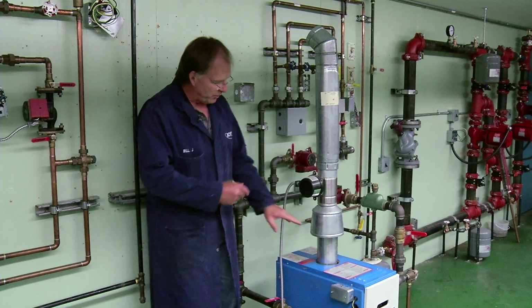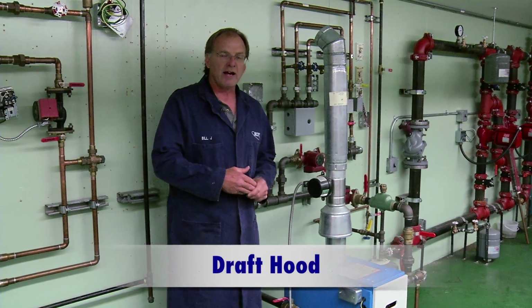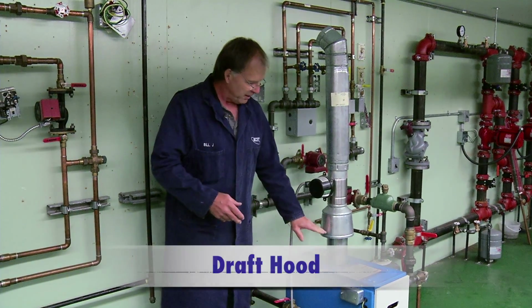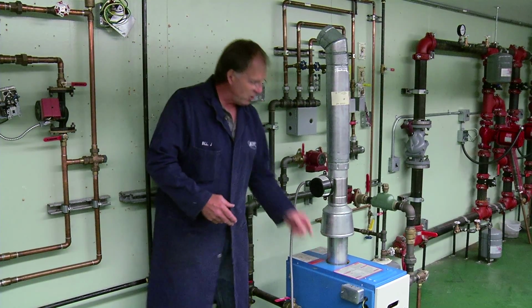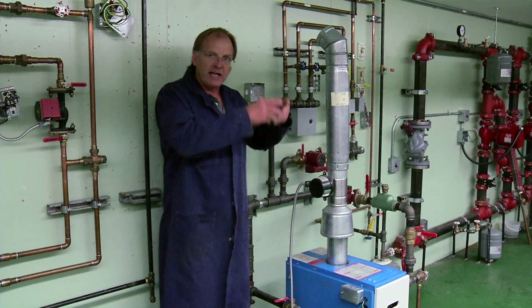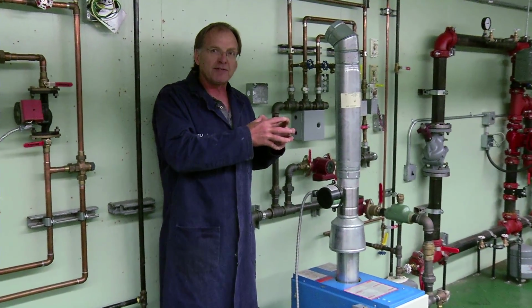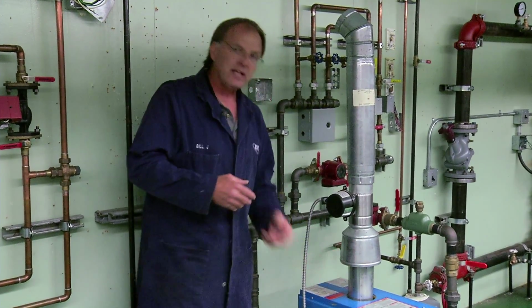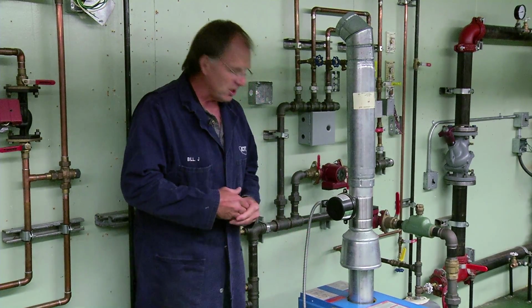So what we do is we install what they call a draft hood. This basically allows air to go up to the stack. When the stack gases are pulling and there's too much draft, the air will be pulled in from the house. That keeps the burner and the combustion chamber at an atmospheric pressure, which is where it was designed. Now, it's these openings that cause the problem when we talk about energy efficiency.